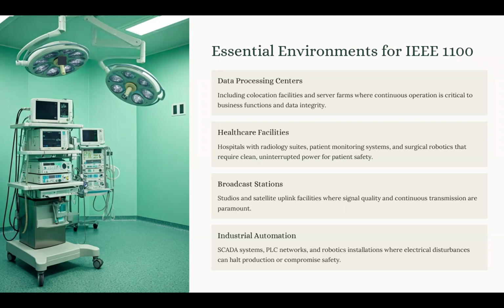One of the other recommendations is to have a clean power supply, which normally is a double conversion UPS system with plus or minus 2% voltage regulation and plus or minus 0.1 hertz frequency regulation for radiology suites.